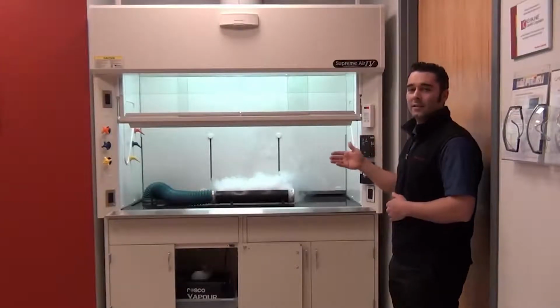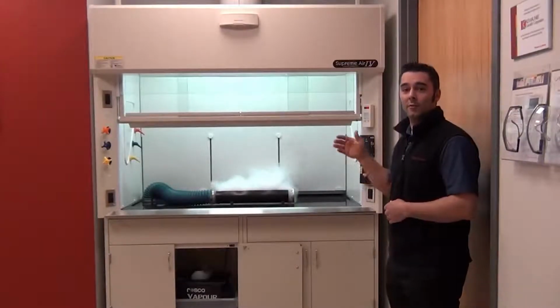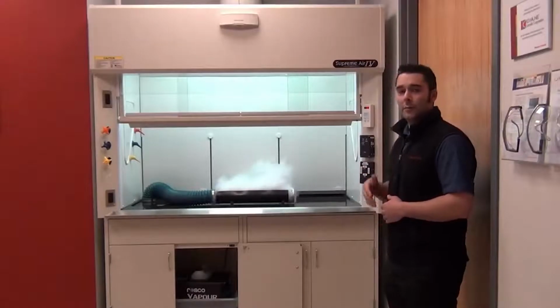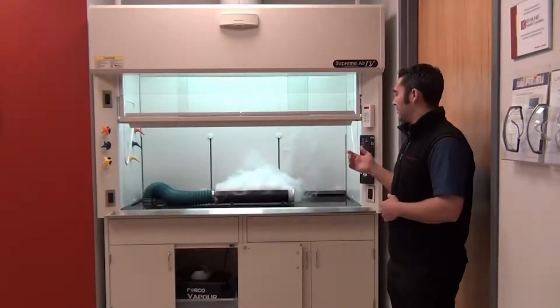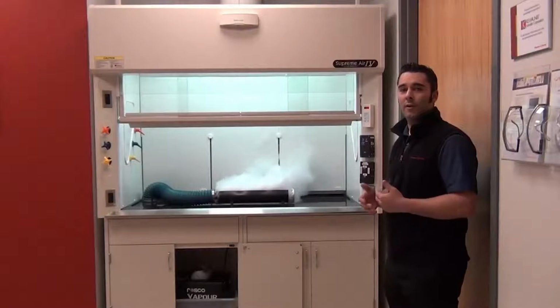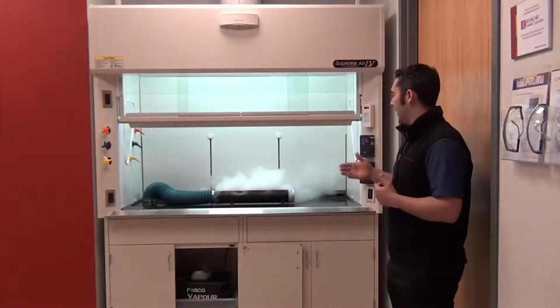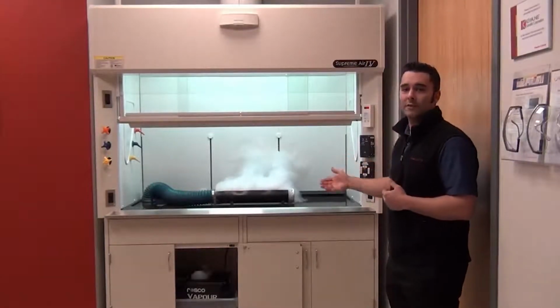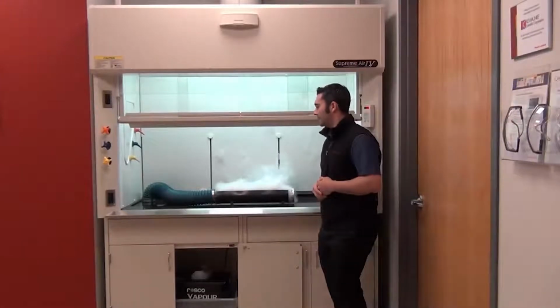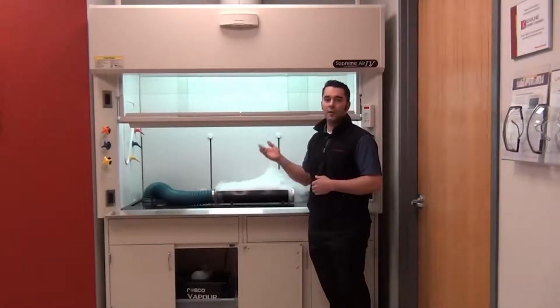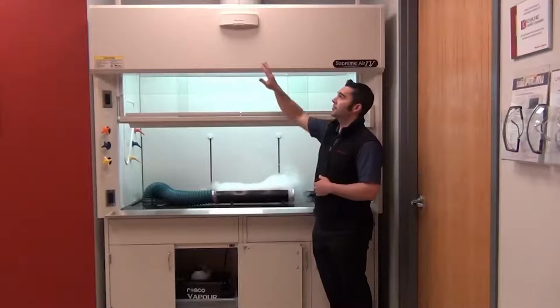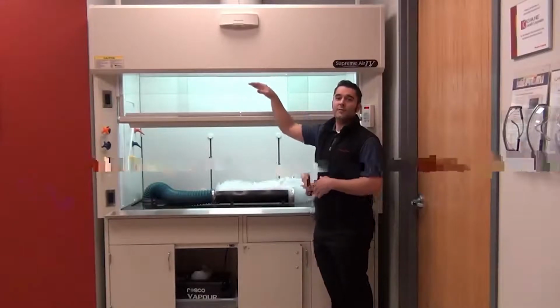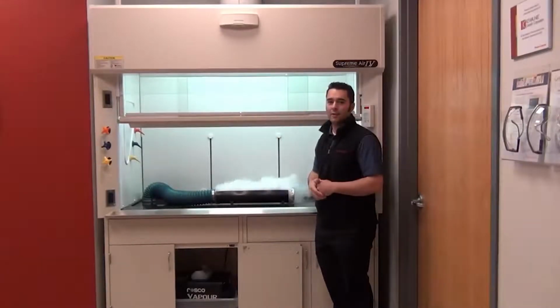Again, you can see that the chemicals inside of the hood slow down when it's at 60 feet per minute, but per the ASHRAE standards, having 60 feet per minute in that hood when nobody is in front of it is still acceptable, and I can prove it here by no loss of containment. Again, when I walk up to this thing, it's immediately going to go back to 100 feet per minute. So that's how the zone presence sensor helps save energy without any human interaction.